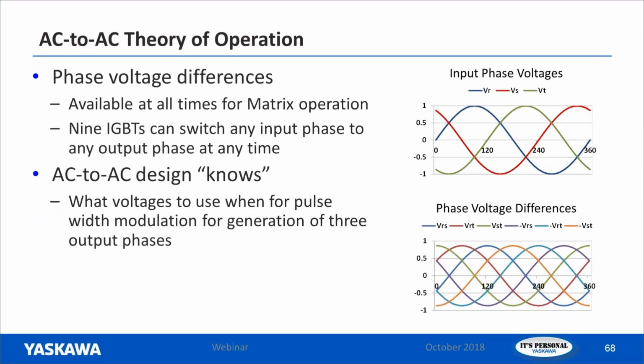A little bit more on the theory of operation of the Z1000 drive. Z1000U HVAC matrix. At any given time, it knows what the voltage is on any of the 3 input phases, and it's going to be different on each of the 3. So it can pull any voltage it needs from any spot on the front end to create the output voltage waveform going out to the motor.